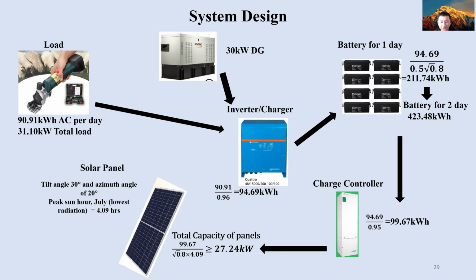So we got the average load of 90.91 kilowatt hour AC from the load calculation, and we chose an inverter of 96% efficiency, which gives the DC energy of 94.69 kilowatt hour. This much energy must be supplied from the battery. So we chose a battery depth of discharge of 50% and a round trip efficiency of the battery of 80%, which gives 211.74 kilowatt hour of capacity for 1 day.